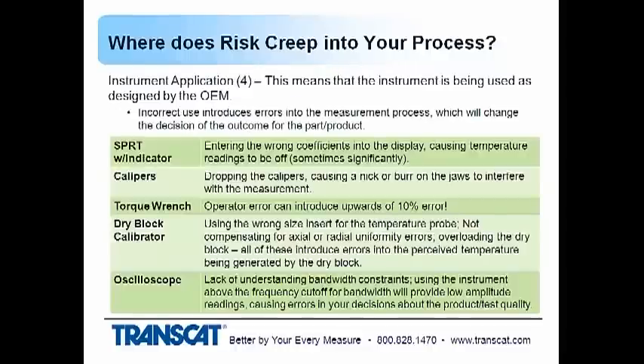The application, and that's what that leads to, is the correct use of the instrument. Incorrect use can introduce errors that can cause you to have a different outcome of your decision whether the product's good or bad. A few examples here. If you have a platinum resistance thermometer with an indicator, the way that has to be used is that during the calibration a set of coefficients is determined that has to be programmed into the display. There are some types of connectors where that's automatically programmed into the connector and it removes the operator error. Some of the older units, though, require you to enter the coefficients into the display. And if that is left at the old coefficient values, or the wrong coefficients are plugged in, or the probe is changed out without changing those coefficients, you're going to get incorrect temperature readings, and you're going to make wrong decisions about your product or your process.